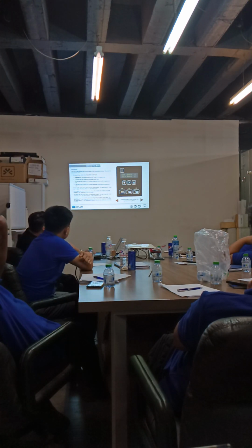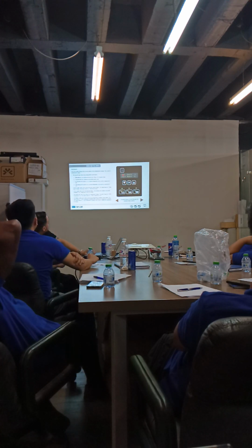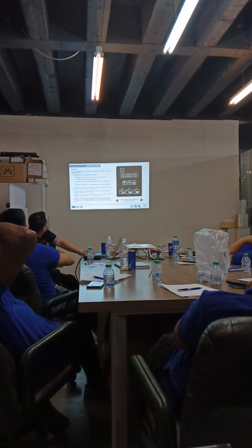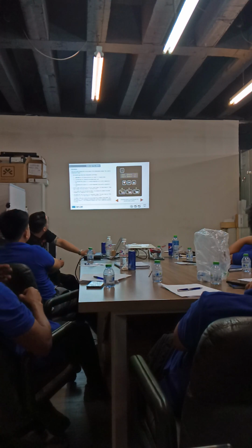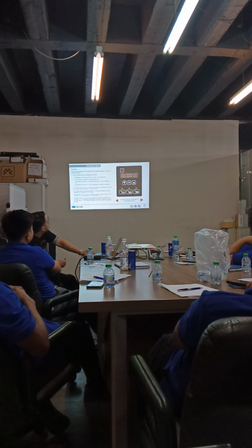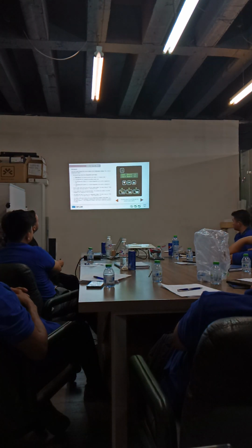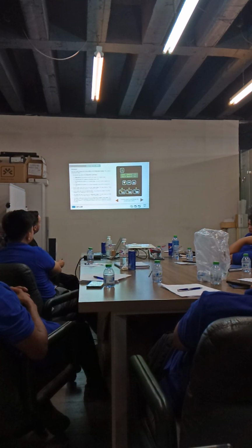So the top left value shows the refrigeration cycle status. Okay, so it's saying cool at the moment. If it said wait, it indicates the system is in a short cycle or in bypass mode. If it says cool, it indicates the system is in cooling cycle. If it says on, it indicates the system is in normal refrigeration. If it says off, it means normal refrigeration and the compressor is off.